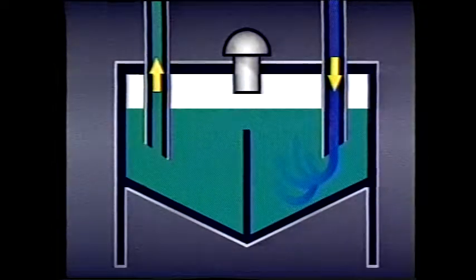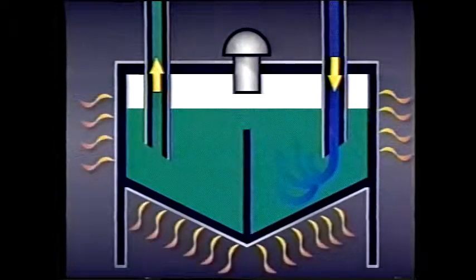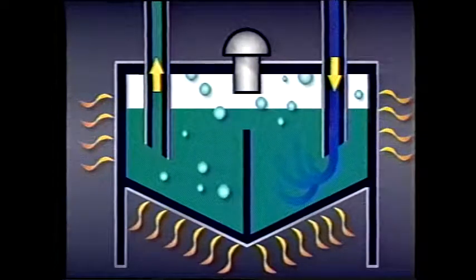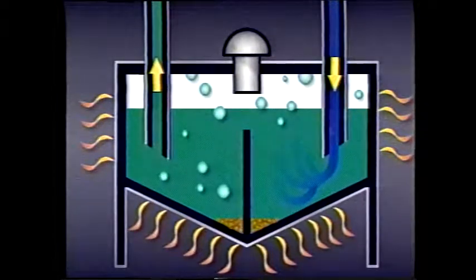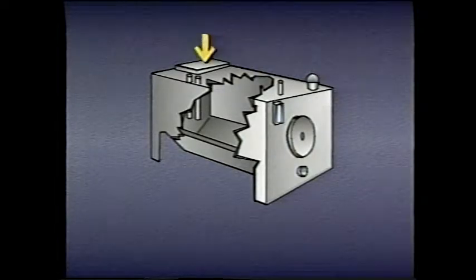Instead, the returning fluid mixes with the other fluid in the tank. The large steel sides absorb heat, cooling the fluid. At the same time, entrained air escapes and a lot of contamination settles out. The reservoir's dished bottom collects the dirt, and an end cover permits occasional clean-out. A drain allows sampling of the fluid. A gauge indicates the fluid level. A filler cap includes a built-in breather to let air escape. A sturdy plate provides a place for mounting the pump and motor.